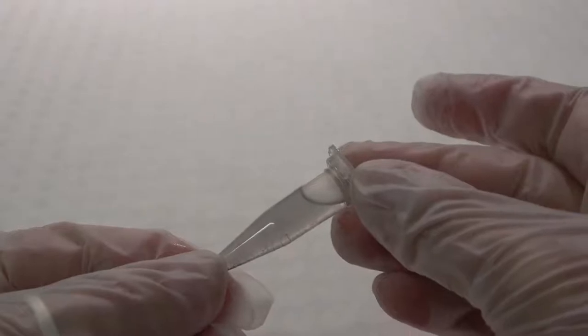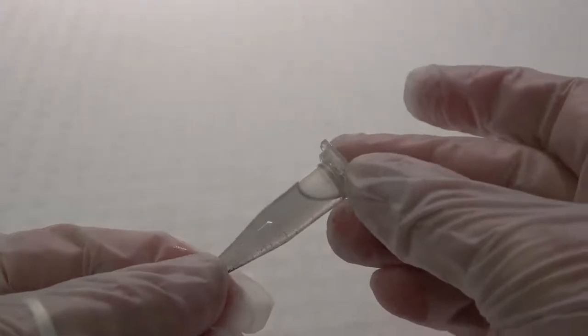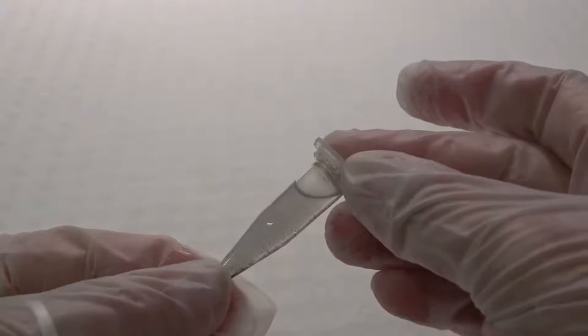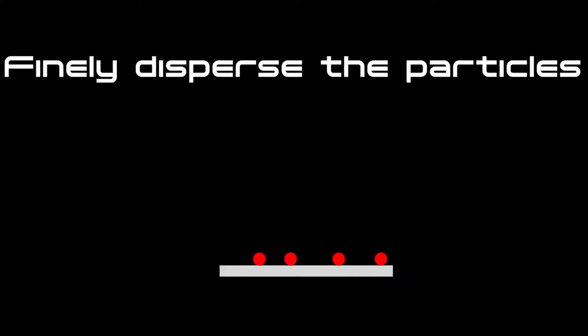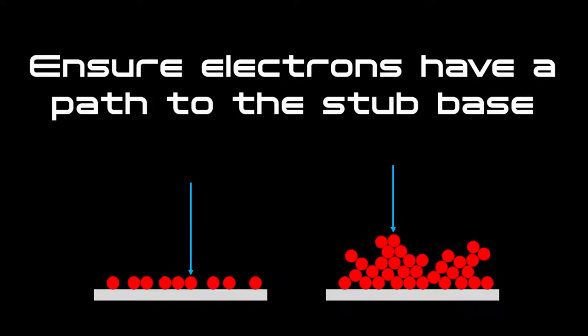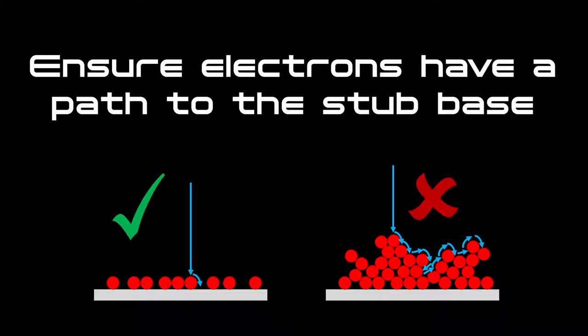The technique described here can also be used to prepare fine non-nanopowdered samples in suspension for SEM examination. When mounting nanoparticle samples for SEM, our main goal is to create as thin a dispersal of particles across areas of the substrate as possible. This allows the particles to adhere to the substrate and ensures that the negative charge generated by the electron beam has a pathway away from the surface of the particles to the substrate.